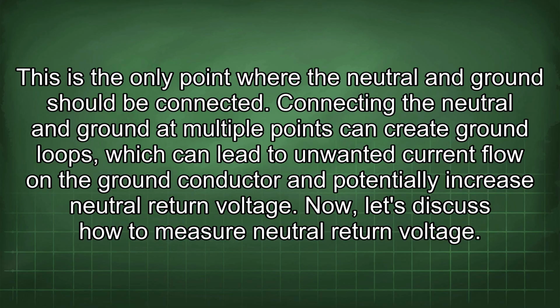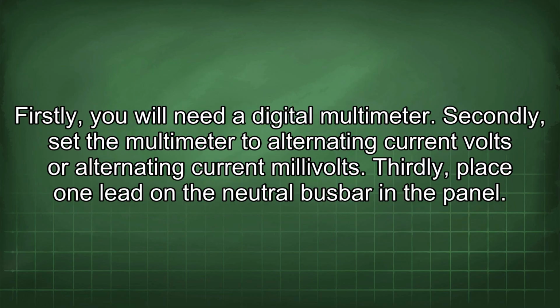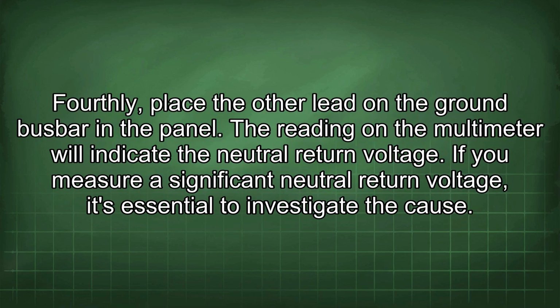Now let's discuss how to measure neutral return voltage. Firstly, you will need a digital multimeter. Secondly, set the multimeter to alternating current volts or alternating current millivolts. Thirdly, place one lead on the neutral busbar in the panel. Fourthly, place the other lead on the ground busbar in the panel. The reading on the multimeter will indicate the neutral return voltage.